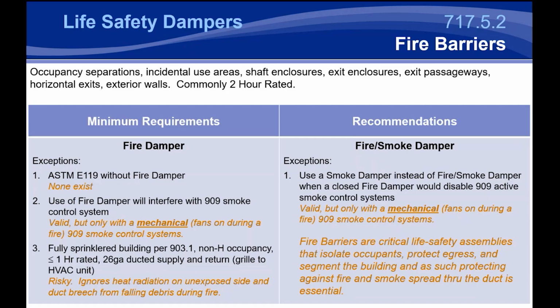Now, one exception that's used quite a bit is if you've got a fully sprinklered building, so you're putting out that fire, the fire is not spreading, and you've got a barrier rated for less than or equal to 1 hour, and it's fully ducted. Now that seems to be a reasonable exception, but it can be a bit risky when you're talking about a building with multiple stories that has the potential for the duct, that 26 gauge duct, to be dislodged. The rationale here is a 26 gauge duct is going to stop any fire from spreading through that barrier from one room to another or across that barrier. And that is the case if the duct remains intact and the smoke or the fire is actually put out very quickly with that sprinkler system.